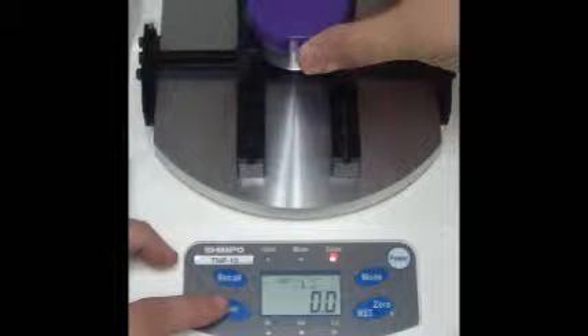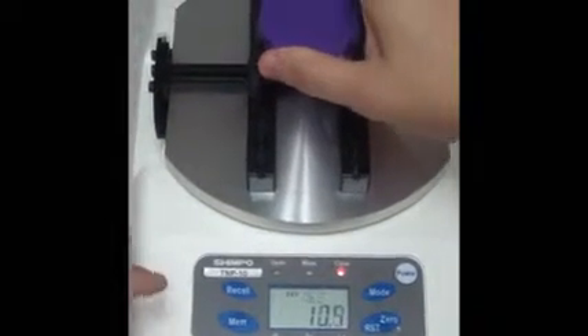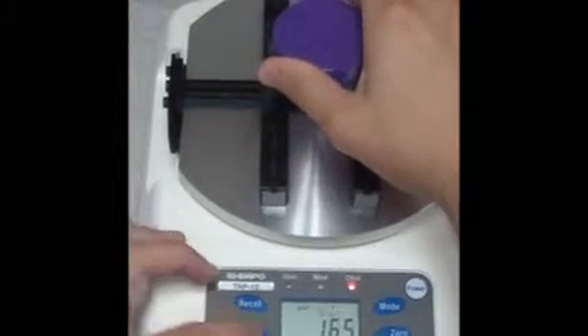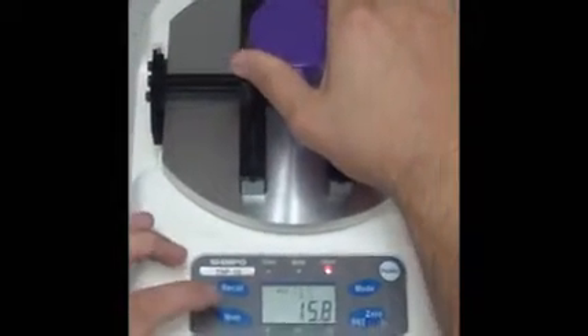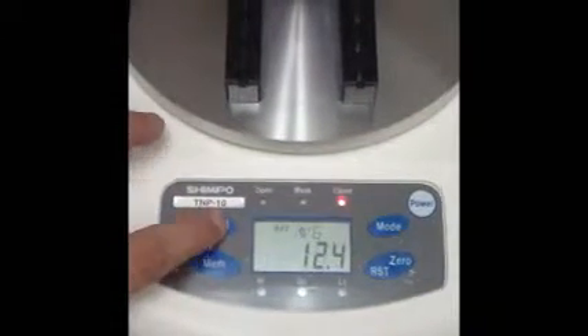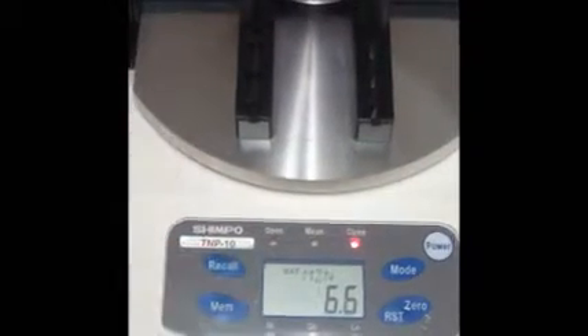Saving data values while performing testing on the TNP torque meter is an easy task to perform. While performing a test, pressing the memory button will allow you to save the data value into the internal memory. You can do this multiple times in a single test. You can display recorded data on the TNP torque meter by pressing the recall button after testing has been completed.